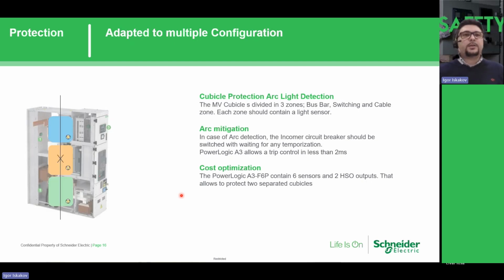If we go like this, we have a sensor in the cable compartment, a sensor in the circuit breaker compartment, and one in the bus bar compartment. With our standalone unit A1 or V121, we were able to protect only one bay with 3 sensors, provide a trip on our circuit breaker, and send a command by digital input to the upper level.